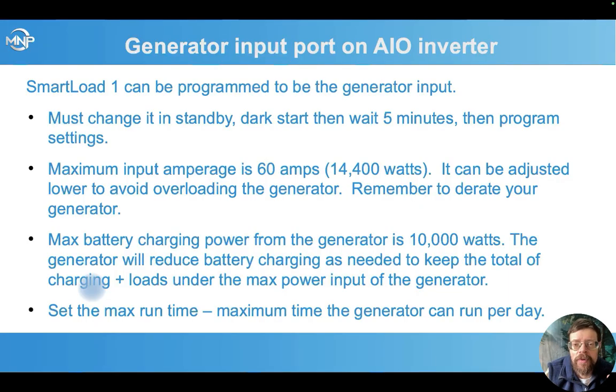Moving on to exactly how it works with our inverter. We have a dedicated generator input, that's smart load 1, and it can be set to be the generator input. To change it, the inverter has to be in standby, and then you'll want to do a dark start of the inverter, turning it off and turning the battery breaker on the inverter off. Wait a minute, then restart it, and wait 5 minutes, then program the settings. That will let it get into its brain that what used to be an output is now an input, and allow all the settings to take effect properly. If you just do it quickly and don't do the dark start, we've had issues where it still shows up as a smart load instead of changing to generator input sometimes.